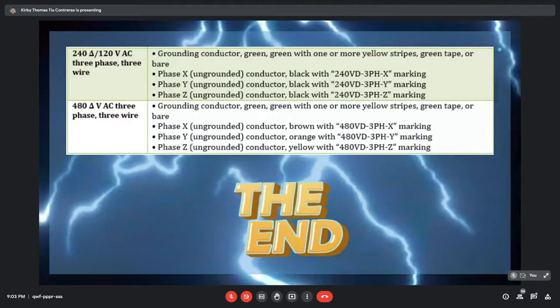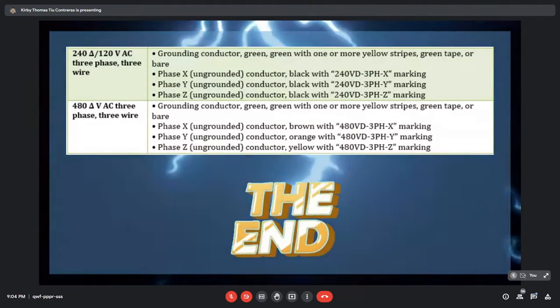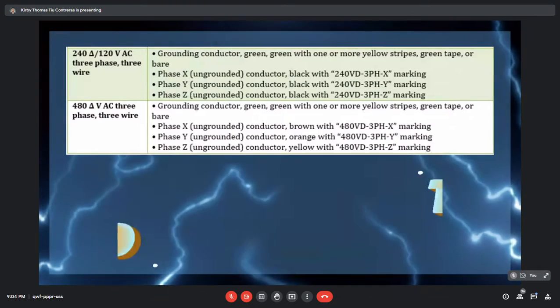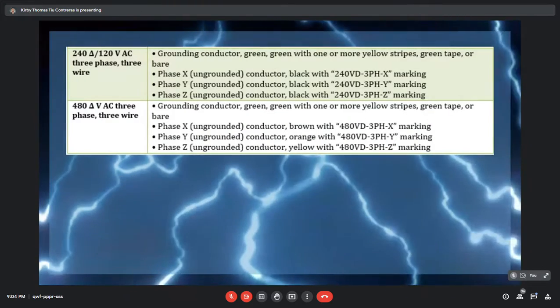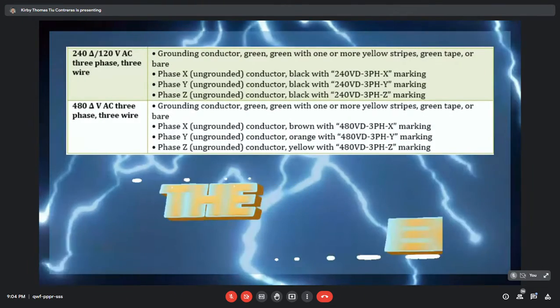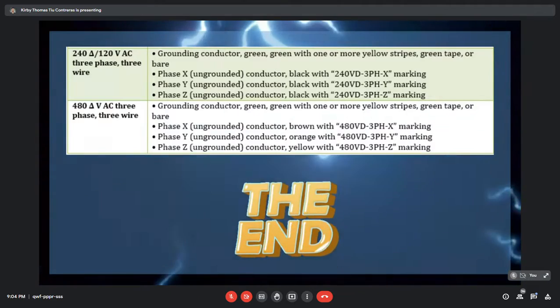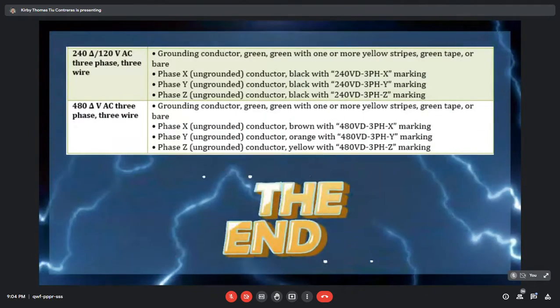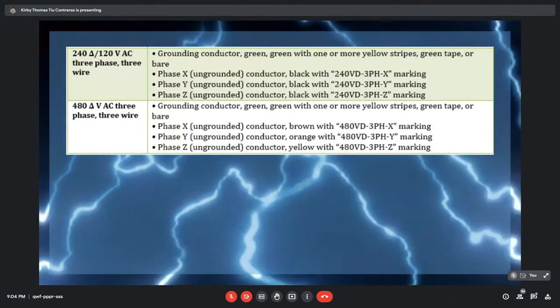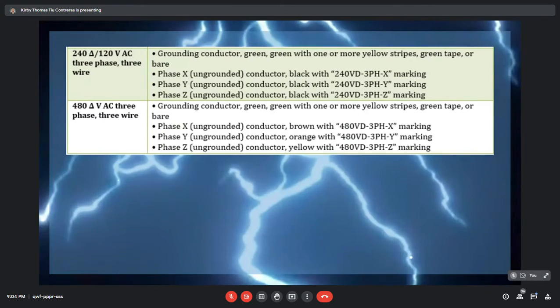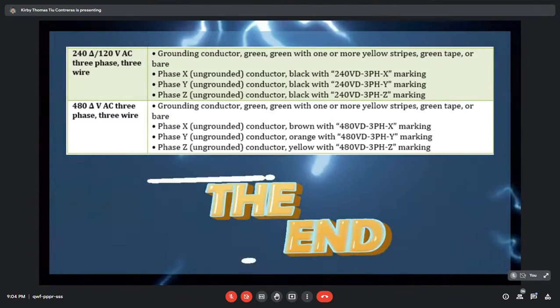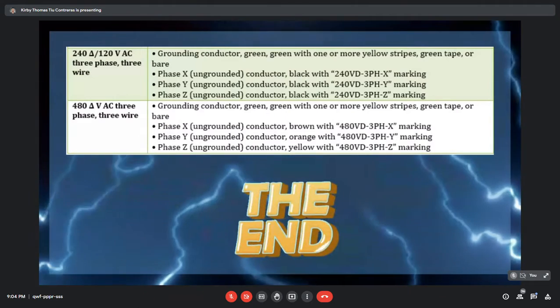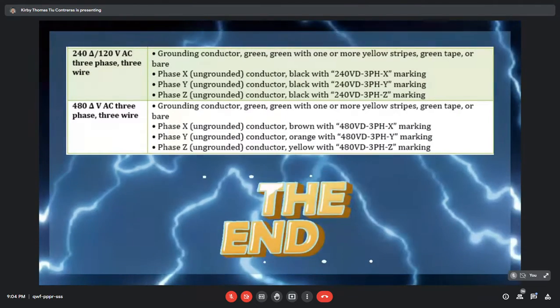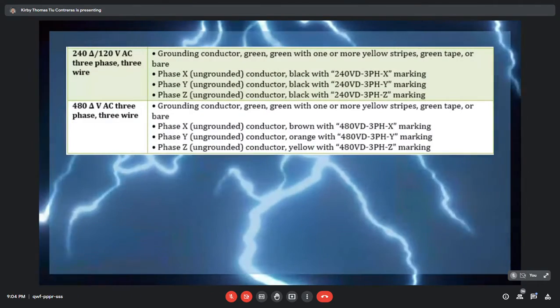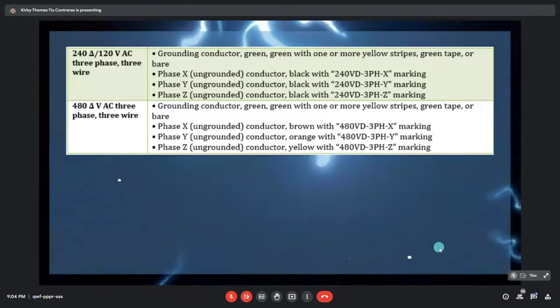And then the last one is the 480 delta volts AC three-phase three wire. Grounding conductor is green with one or more yellow stripes, or green tape, or bare copper conductor. So phase X, Y, and Z ungrounded conductor, color code nila is brown, orange, and yellow. And naa silay marking nga X, Y, and Z sa last nila.